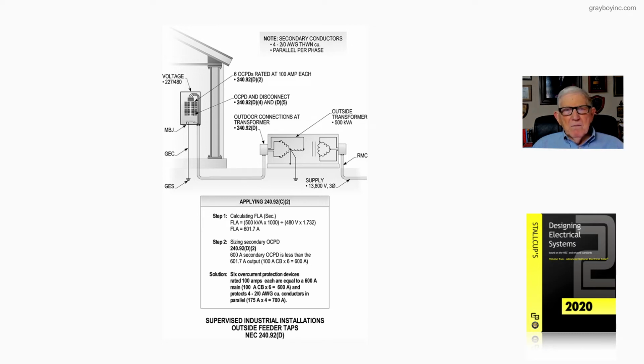Now, with that thought in mind, let's review the boxed-in information, and let's look at the calculation procedure. Note 1, and we're applying 240.92 C as in card 2. We take the 500 kVA transformer times 1,000, divide it by 480 volts times 1.732, and when we perform the math, the FLA of the transformer is 601.7 amps, or rounded up to be 602, whatever you want to do.